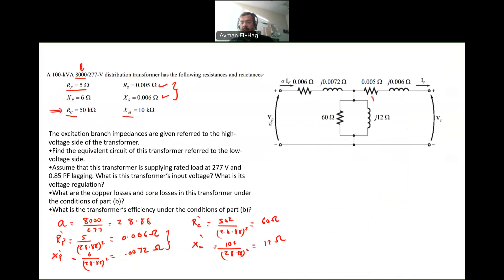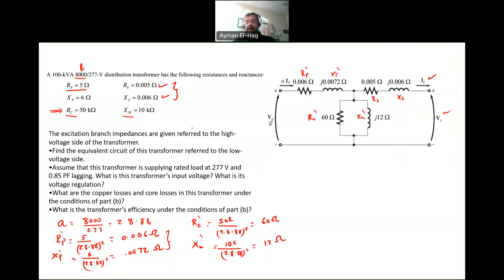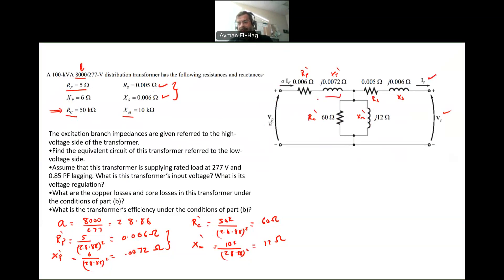So this is your RS and XS as given in the question. This is your RP prime and XP prime referred to the low voltage side, and this is your RC prime and XM prime — the magnetization and core loss branch. When we refer everything to the secondary, IS and VS stay as they are, but the current of the primary will be A times IP, and the voltage will be VP divided by A. This is the exact model, but we can use the approximate model instead.